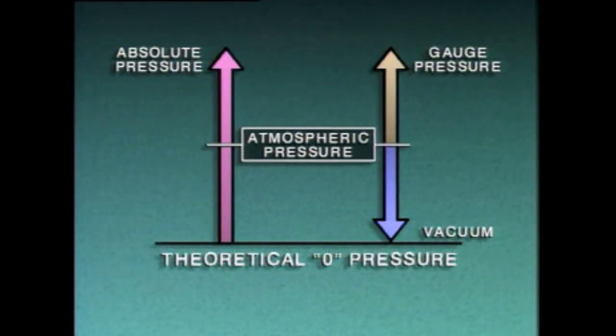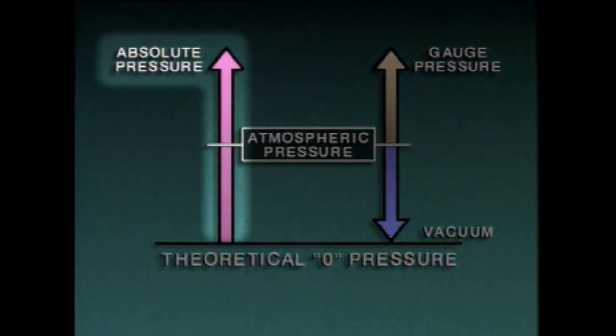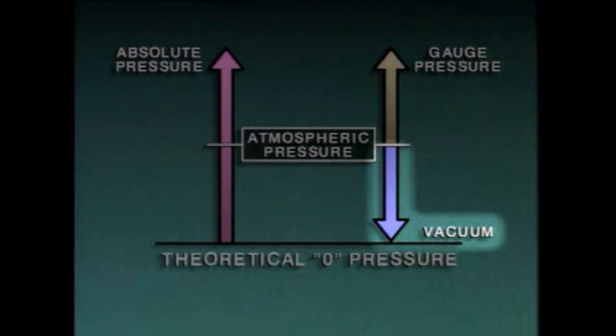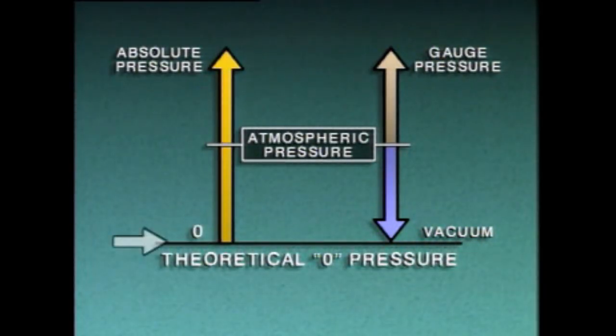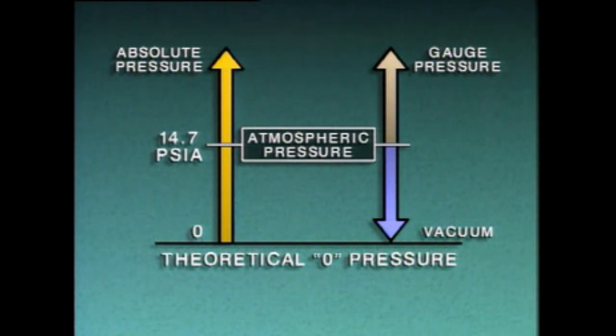The way that atmospheric pressure is taken into account depends on the scale used to measure the pressure. Three scales commonly used for pressure measurements are the absolute pressure scale, the gauge pressure scale, and the vacuum scale. The absolute scale begins at theoretical zero pressure, a condition of no pressure and a total absence of air. On the absolute scale, atmospheric pressure is 14.7 pounds per square inch absolute, or PSIA.